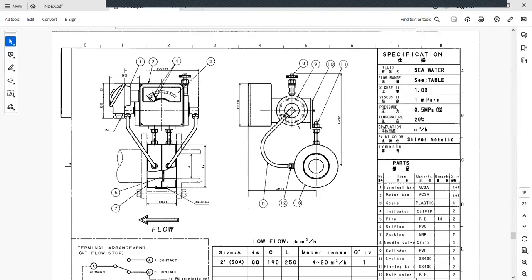The differential pressure transmitter converts readings so one side is high and one side is low, feeding into the meter. Two plastic pipes come out, one to the high pressure side and one to the low pressure side, matching the flow direction. The black needle and red needle are shown - the black should not touch the red needle, and if it does, an alarm is triggered via electrical contact to the control unit.